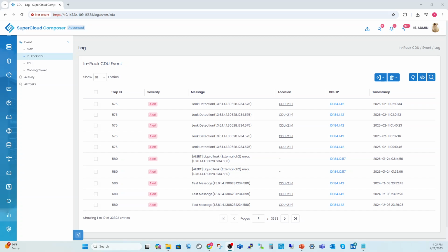Event logs are collected based on a message event or session event extracted through some kind of Redfish API endpoint call to its appliance's BMC. There are two ways today we can extract event logs: collecting event logs for a given server, which certainly doesn't scale, and the other way by initiating a task for log collection of multiple servers, CDUs, cooling towers, and PDUs.